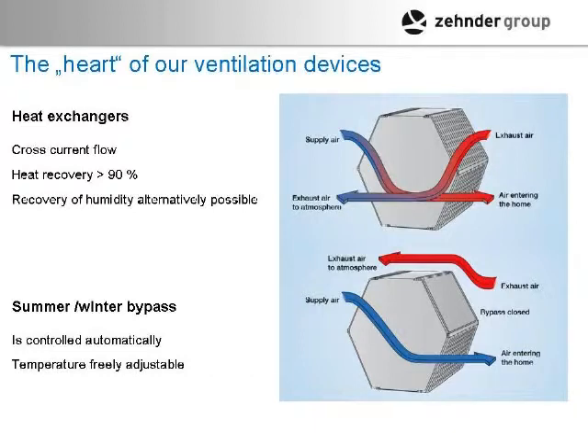What does that mean, 90%? Does that mean that the air comes back in at just 10% of temperature? So if it was 70-degree air going out, it comes back in at 63 degrees, or does it mean something else? Does it have to do with joules? No, the differential. If the air inside is 70 and the air outside is 20, that's a 50-degree difference. 90% of that is made up. So it would be coming in at about a 4.5-degree difference.